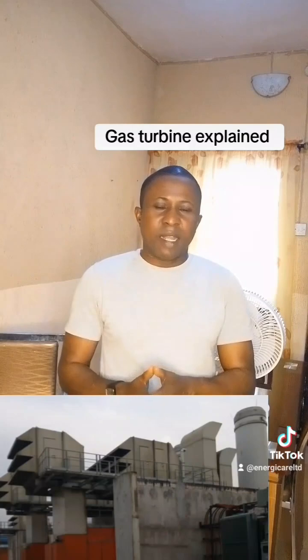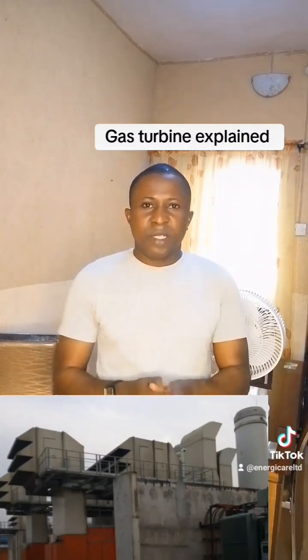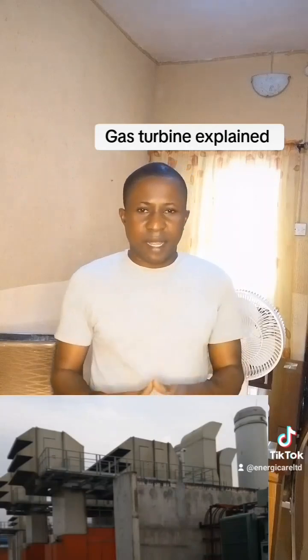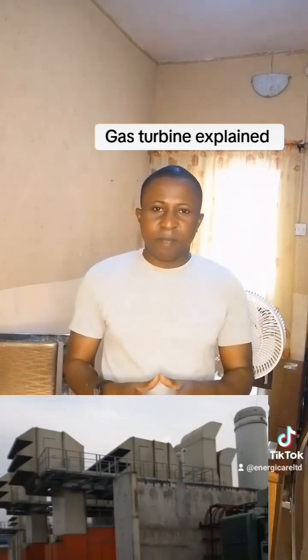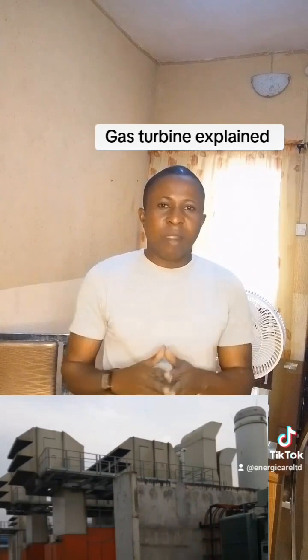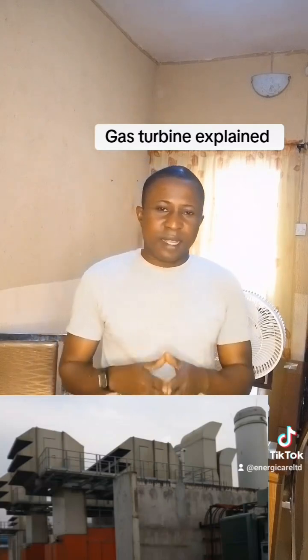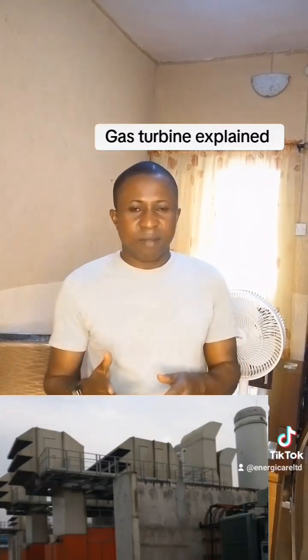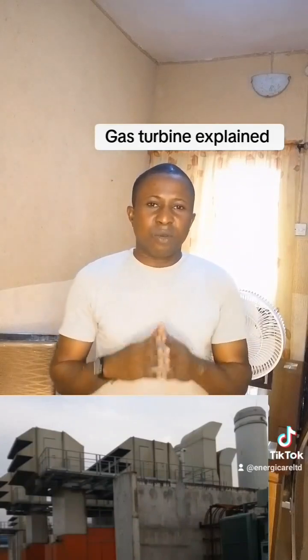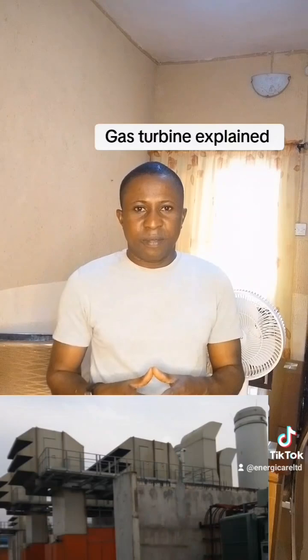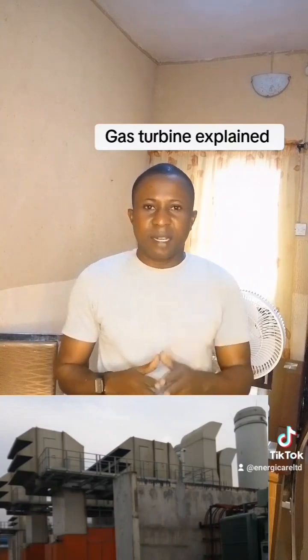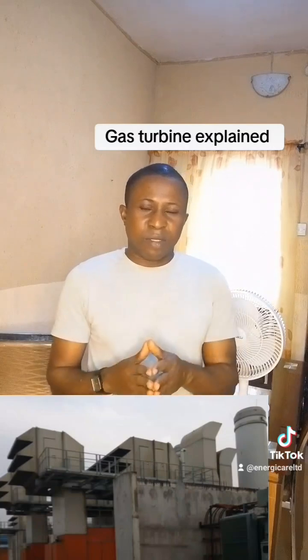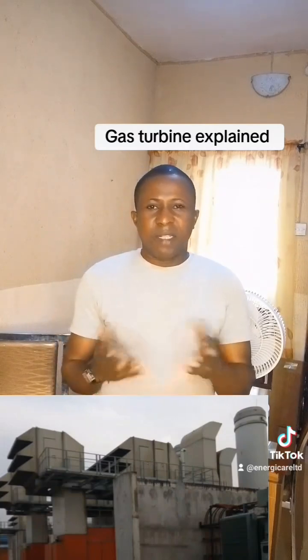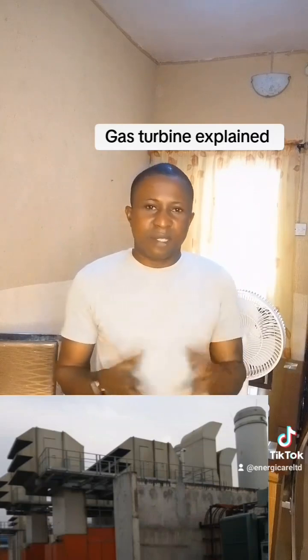Now let's go back to the compressor. The function of the compressor is to compress the filtered air from the filtration system. Some compressors have 15 stages, some 17 stages, depending on the capacity of your turbine. A quarter of the compressed air is used for combustion process, while the rest is used for cooling the combustion product at the turbine first stage inlet, because the combustion product has high temperature, that is above 700 degrees Celsius.